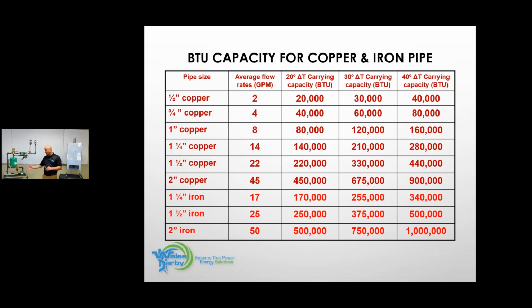I go here to an 80% cast iron product. I take that same dollar bill out and I feed it to my boiler. And if things are running good, 80 cents out of that dollar are going to stay within my home and 20 cents are going to be going out of the flue pipe. I want to keep as much of that in my house as possible. So sometimes I'll design the boiler circuit at a 30 to make it condense more.